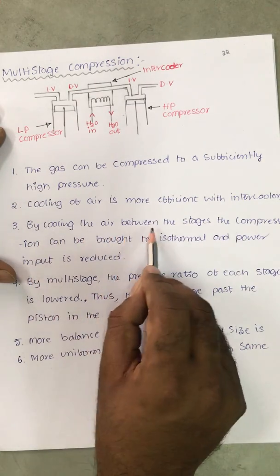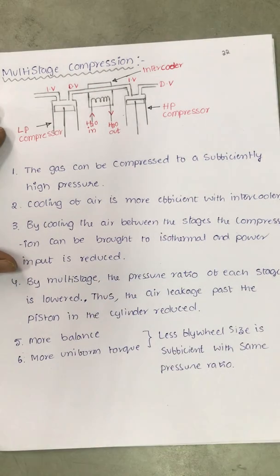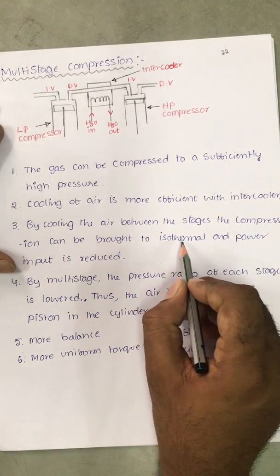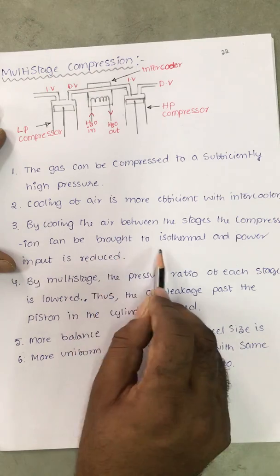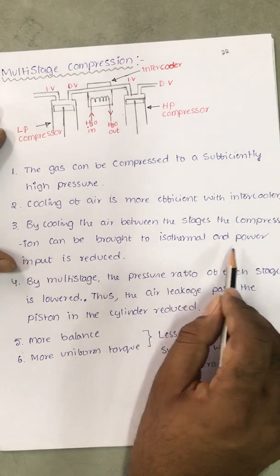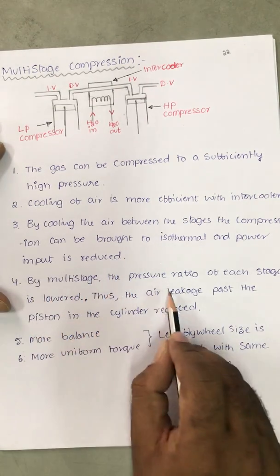The gas can be compressed to a sufficiently high pressure, and cooling of air is more efficient with the intercooler. By cooling the air between the stages, the compression can be brought close to isothermal. Since isothermal compression requires minimum work input, once the compression is isothermal, power input is very much reduced.